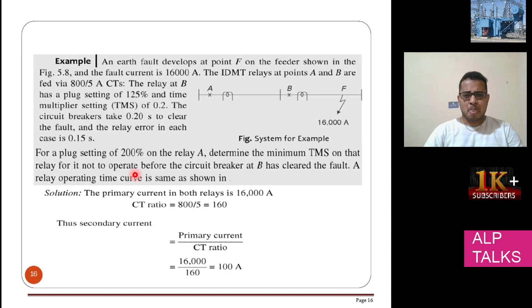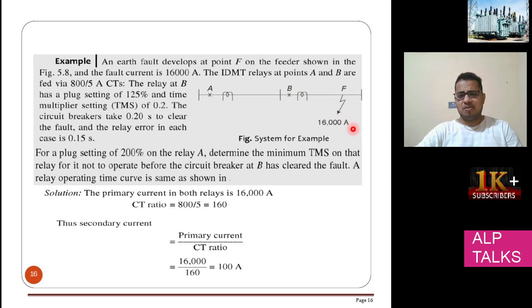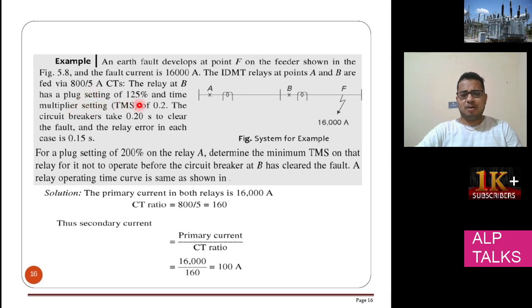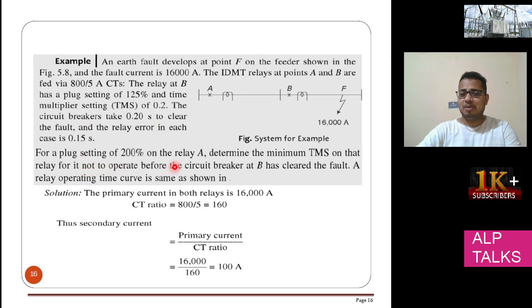Here is another problem. You have a line with two relays at A and B, and C also present. The fault current is around 16,000 amperes. A CT of 800/5 amp is used, with a plug setting of 125% and a time setting of 0.2 seconds at B. The circuit breaker will take 0.2 seconds to clear the fault, and there is a relay error of 0.15 seconds. The plug setting for A is 200%. The question is: what is the TMS — how much time will it take for A to operate?